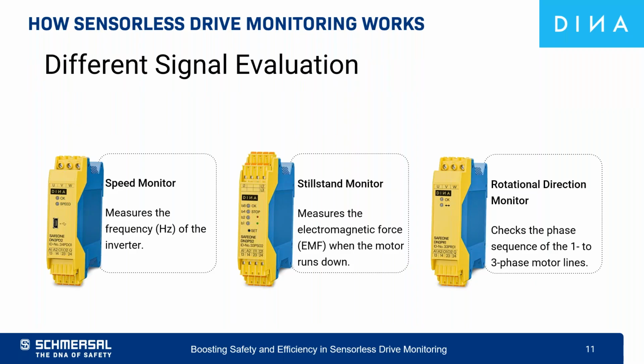The standstill monitoring module measures the electromagnetic force, EMF, the induced residual voltage. How it works: as long as the motor is turning, a voltage is measured, regardless of whether the motor has been switched off or is still running. This is because every asynchronous or synchronous motor acts as a generator, producing a small voltage that our module can detect. The standstill monitor detects the safe stop when the measured voltage falls below a defined threshold, near 0 volts. This is used for monitoring safe standstill. This module can also be used for both 3-phase and 1-phase motors.